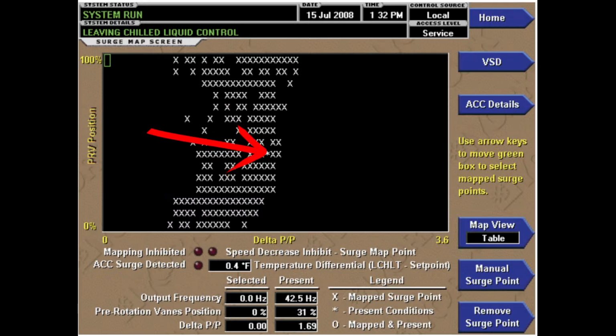That little asterisk is indicating that this is where we're at currently on the map. This says output frequency. Yeah, so the system is trying to add, anyway, ignore this map. You can see down here, this is where you're actually at, the present condition. So it'll float around on this to show you where you are. And you can manually add these points.